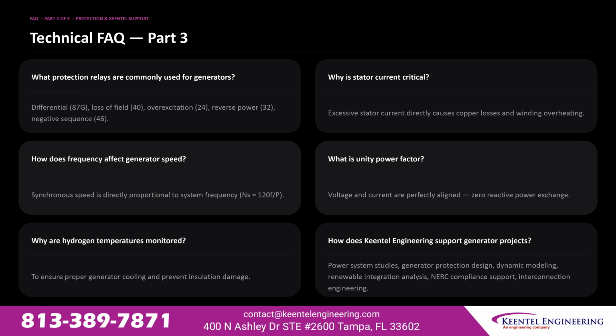What protection relays are commonly used for generators? Differential, loss of field, overexcitation, reverse power, and negative sequence. Why is stator current critical? Excessive stator current directly causes copper losses and winding overheating. How does frequency affect generator speed? Synchronous speed is directly proportional to system frequency. What is unity power factor? Voltage and current are perfectly aligned. Zero reactive power exchange. Why are hydrogen temperatures monitored? To ensure proper generator cooling and prevent insulation damage. How does Keentel Engineering support generator projects? Power system studies, generator protection design, dynamic modeling, renewable integration analysis, NERC compliance support, and interconnection engineering.